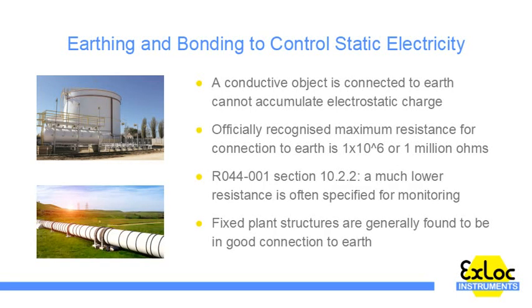Details of these calculations may be found in R044001, section 10.2.2, which also states that conductors in good contact with earth have a resistance to it of less than 10 to the 6 ohms, and for convenience, a much lower resistance in the range of 10 to 100 ohms is often specified for monitoring.